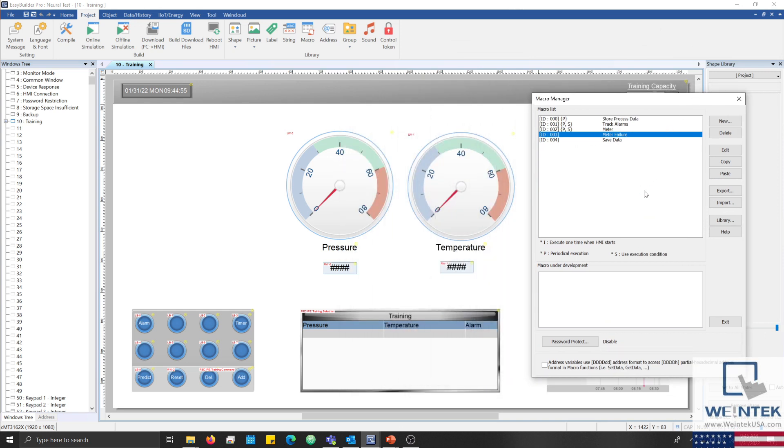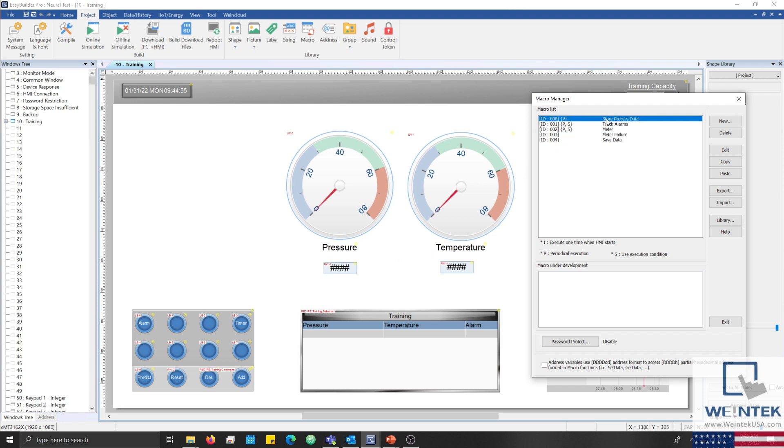Now, to give us an idea as to how this project sources data for our algorithm, we begin by saving process data to retentive memory every 15 seconds. This action is performed by the storeProcessData macro. If an alarm is triggered, the data stored within retentive memory is saved within our recipe database by the trackAlarms macro.